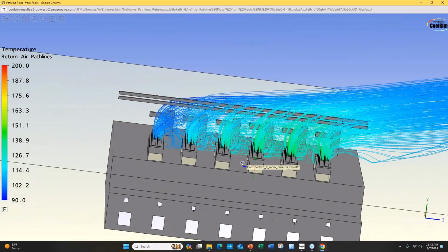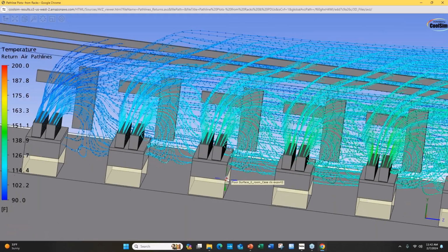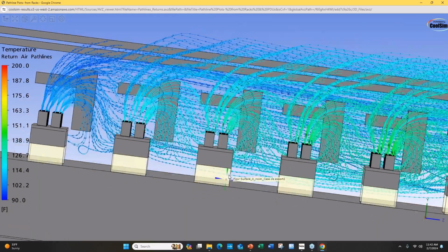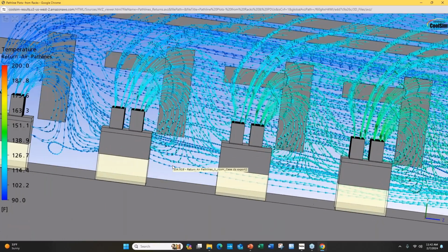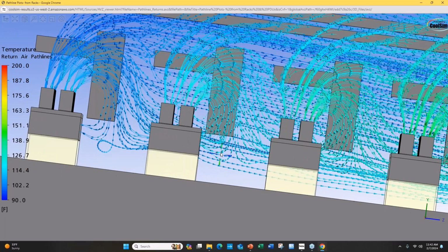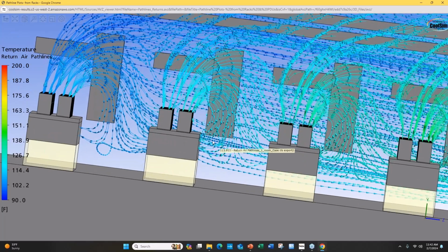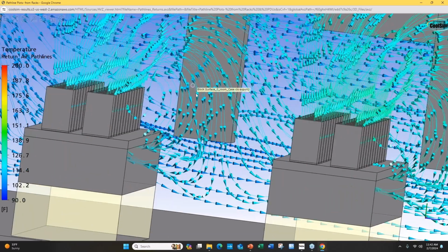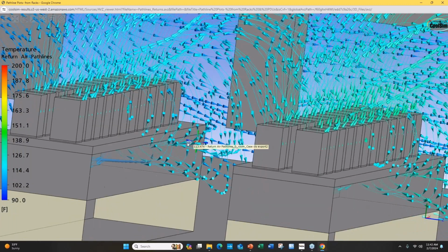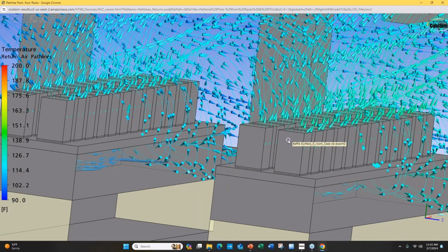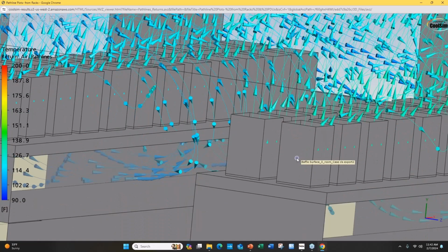Again, I wanted to show you some of the re-entrainment that occurs. Now here, there's chimneys that have been put on top. So this comes a little bit later in the cycle than prior. But what we're seeing a lot of here is re-entrainment right from the exhaust into the intake. And you can see chimneys have been added. In this case, the chimneys are made using baffles, 4 baffles, and then cloned. You can also simply make your HDUs taller so that the outlet is up higher that mimics the effect of a chimney. You can do it either way.